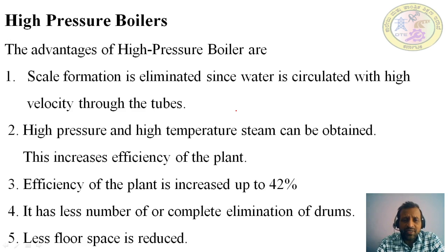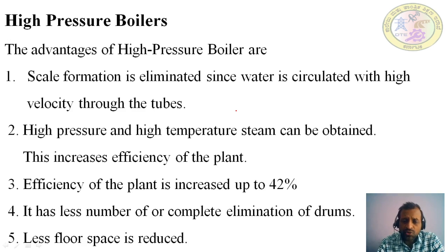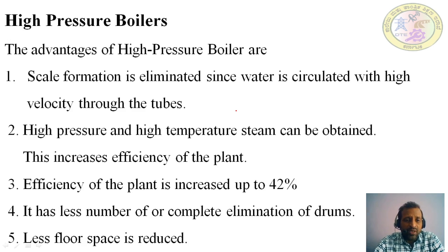The first advantage: scale formation is eliminated since water is circulated with high velocity through the tubes. In the low pressure boilers we studied previously, the water flows slowly. When the velocity is slow, impurities and sediments present in the water get deposited on the inner surface of the tubes, causing scale formation. During maintenance or repair, you need to replace those tubes again and again. To eliminate this disadvantage, we use high pressure boilers.